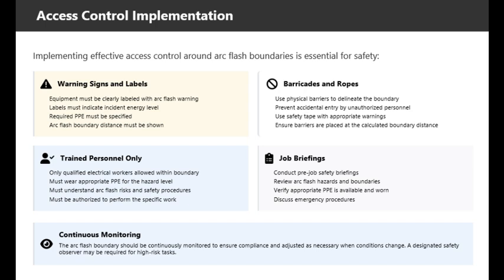The labels serve as a constant reminder of the hazards present and the precautions required. Barricades and ropes provide physical barriers to delineate the arc flash boundary and prevent accidental entry by unauthorized personnel. Use safety tape with appropriate warnings, and ensure barriers are placed at the calculated boundary distance. Physical barriers are especially important in areas where multiple workers or contractors may be present.